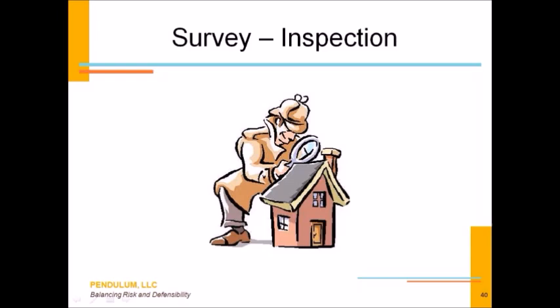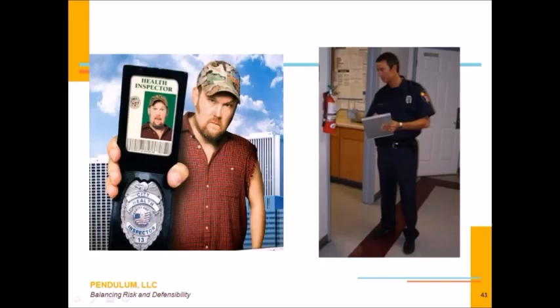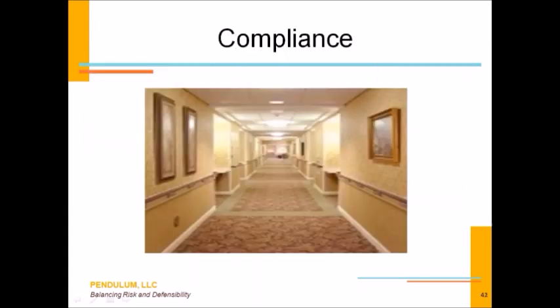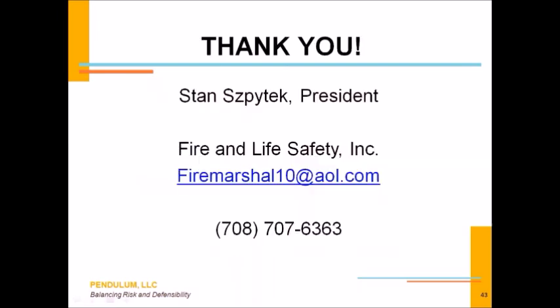Your team, not only your facilities management staff, but even line staff through all levels of your organization, need to know life safety 101. They need to know that everything needs to be to one side or the other. They need to be trained on keeping those storage closets, those linen rooms, to a storage height that's 18 inches below the bottom of those sprinkler heads. They need to know RACE and PASS like the back of their hand. Because regardless of the authority having jurisdiction that you're dealing with, whether it's the good-looking fire inspector from your local jurisdiction, whether it's that county health inspector, the state inspector, or a federal surveyor, or your accreditation team, you've got to be prepared for survey, because it is about compliance. We've got to be ready for anything.